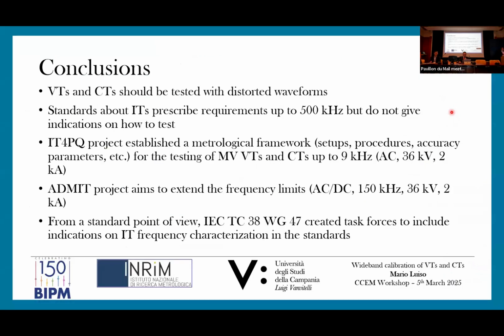So in conclusion, voltage and current transformers should be tested with distorted waveforms. Currently, standards about instrument transformers prescribe requirements up to 500 kilohertz, but do not give indication on how to test them. The IT4PQ project established a metrological framework in terms of setups, procedures, and accuracy parameters for the testing of medium voltage VTs and CTs up to 9 kilohertz.